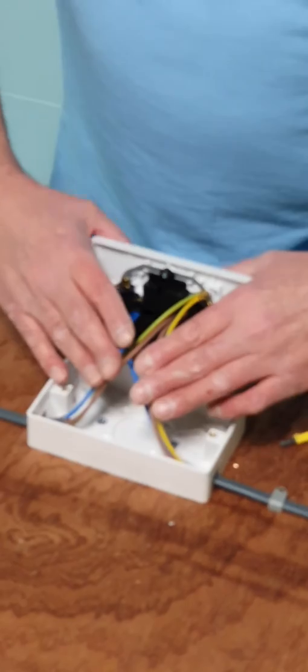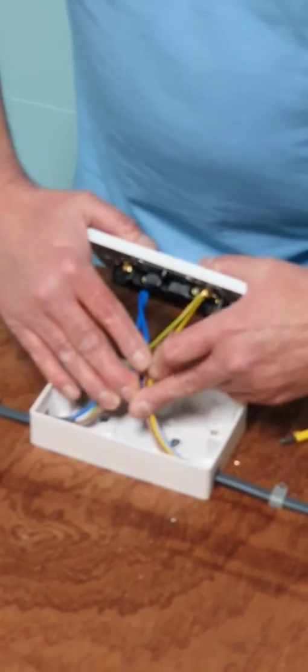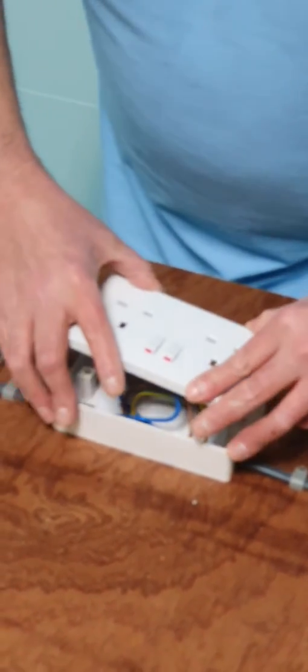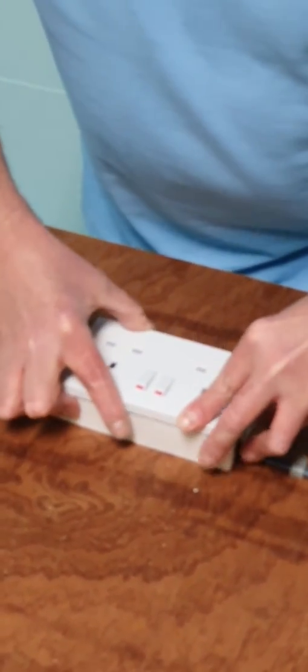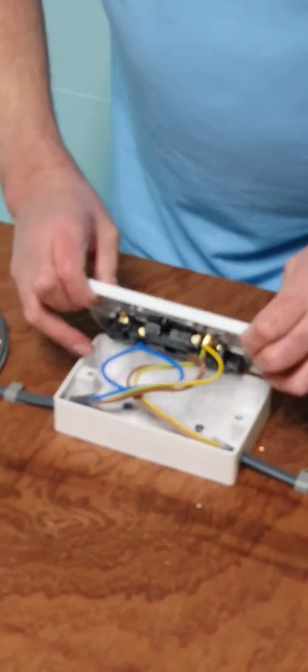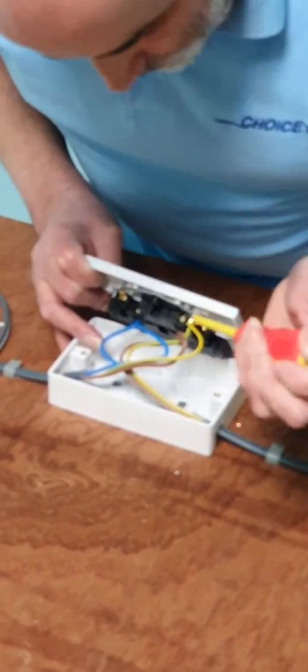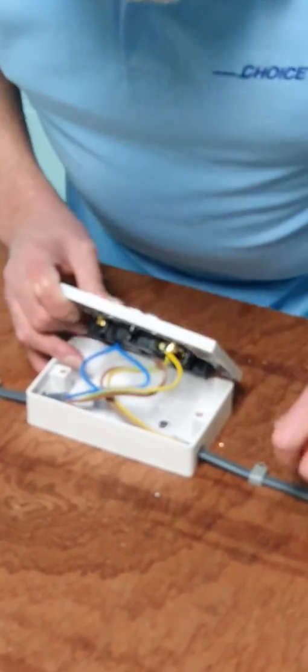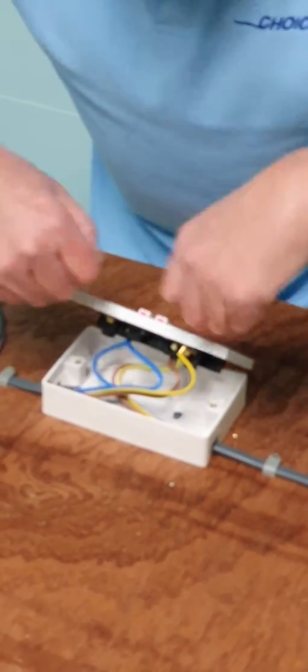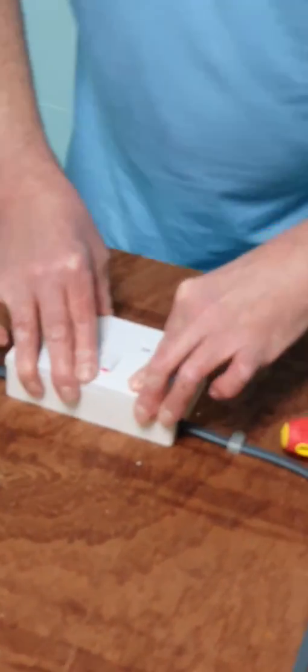Now we've got this up and into our terminals. We need to very gently flatten away our cables. This is where we have a bit of a sort of spring effect. You can shape these into the box. And then again come back out and just very gently make sure that one came a little loose. Give them another slight nip up. You can see they're nicely bent around in like a spring action. You don't want any tight and pinched in there.